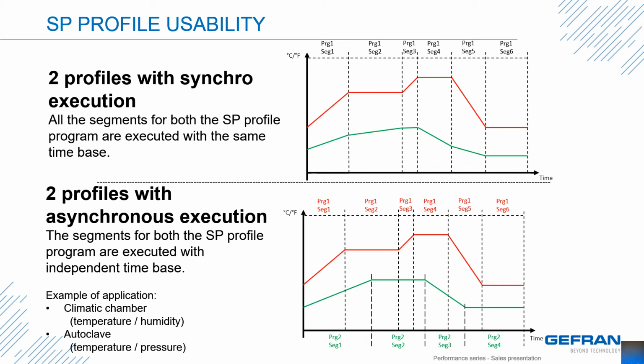Within Express, you can set up synchronous profiles. At the top is a 2-channel PID unit. They share the same time-based segments. Maybe these are both temperature profiles, but they could be temperature and humidity. If segment 1 is 30 minutes, then it's the same for both profiles. I say they are shared time-based, but if there's a holdback function set or a guaranteed soak, then one channel will wait for the other to reach the target before advancing to the next step. I mentioned heat treat earlier because it's possible to have the 2 probes measuring temperature, but if one area doesn't get the needed heat, then the holdback function could extend the time base out, getting the parts properly processed.